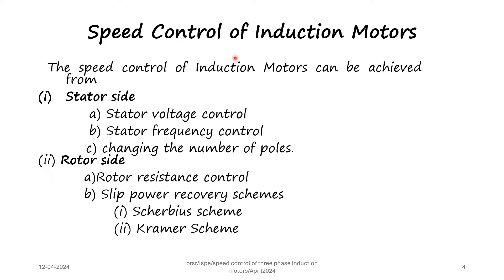Speed control of induction motors can be achieved from the stator side and rotor side. From the stator side there are three possible methods: stator voltage control, stator frequency control, and changing the number of poles. From the rotor side the methods are rotor resistance control and slip power recovery schemes. Under slip power recovery schemes there are two schemes: Scherbius scheme and Kramer scheme.